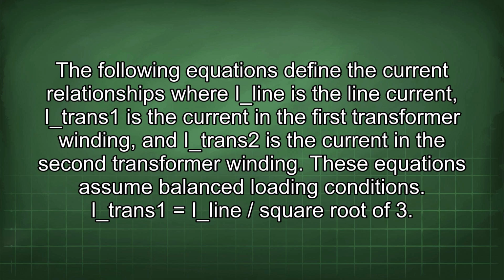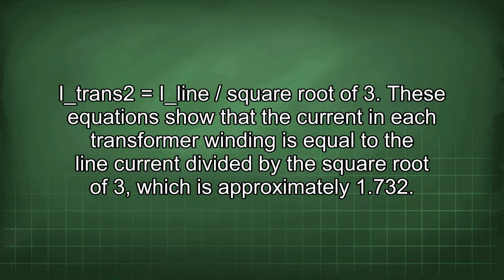I trans equals I line divided by the square root of 3. I trans equals I line divided by the square root of 3. These equations show that the current in each transformer winding is equal to the line current divided by the square root of 3, which is approximately 1.732.